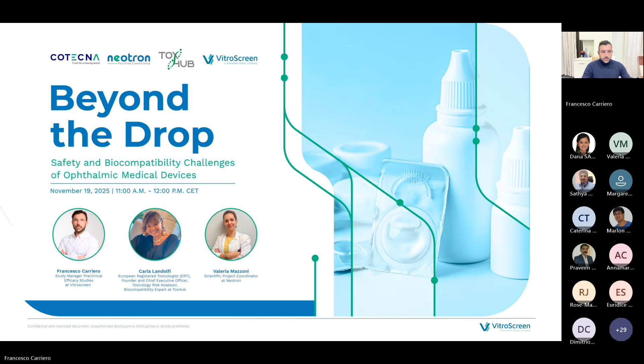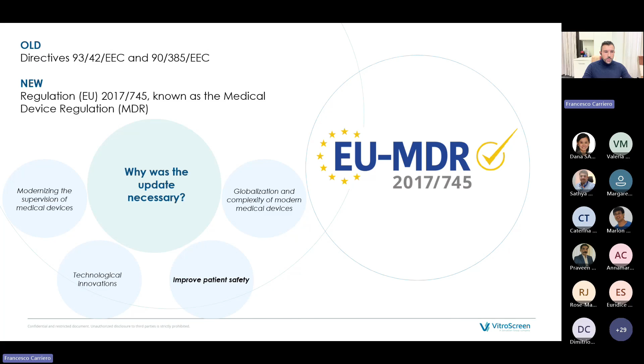Okay, perfect. Taking a step back, the regulation of medical device has undergone a very important update in recent years. Regulation 2017-745, known as the Medical Device Regulation MDR, replaced two old directives, 93 and 90, entering into full force in May 2021. The aim of the new regulation, which is designed to ensure the safety, performance, and transparency of medical devices, was to fill the significant gaps in the old regulatory framework, in line with modernizing the supervision of medical devices, the technological innovations, the globalization and complexity of modern medical devices, and last but not the least, to improve patient safety.